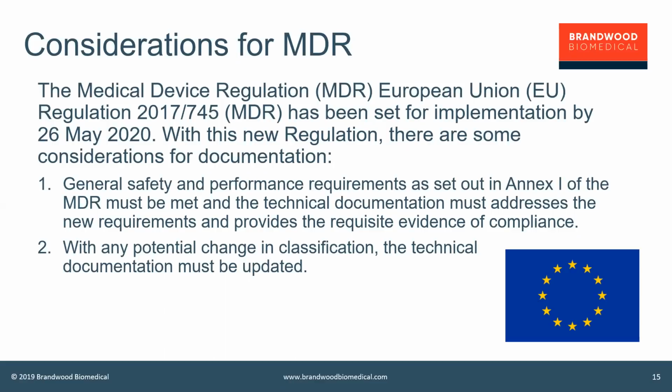And effectively, just like the ER checklist, you need to make sure that your technical documentation addresses those requirements and provides requisite evidence for compliance. So just like you would with the ER checklist currently under the MDD, you are going to create your checklist. You are going to provide whether that requirement is applicable or not applicable. If it's applicable, you need to provide evidence through documentation, references that you comply and have met that requirement.